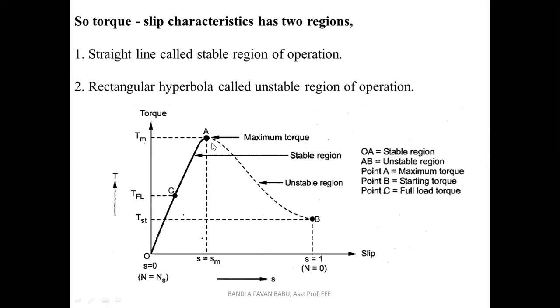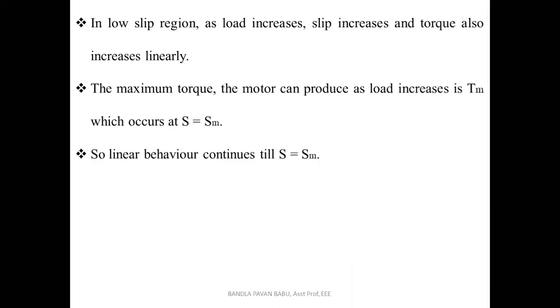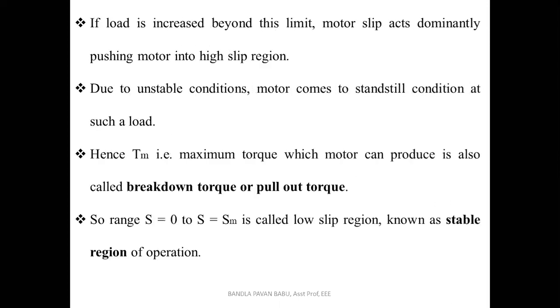In our simplified analysis, for our convenience we can call it the breakdown. Earlier we have seen that it basically comes in the parallel part, right? So that is the tolerable range. If it exceeds, it comes under the unstable region and anything may happen. Anything in the sense that in the induction motor, the rotor may be stopped. If it suddenly stops, there will be a huge amount of current and the windings may get damaged. Those are some of the failures.